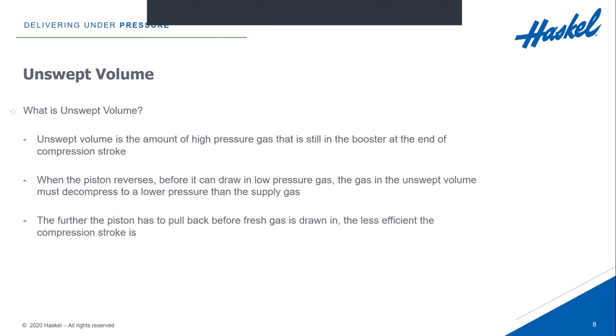Another important aspect of gas compression is the unswept volume inside the compression device. The unswept volume is the amount of high-pressure gas that's still in the booster at the end of the compression stroke. All compressors, no matter what the technology, will have some amount of unswept volume left in them at the end of the stroke. When the piston reverses, before it can draw in fresh low-pressure gas, that gas in the unswept volume has to decompress to a pressure lower than the supply gas to allow it to flow in. The further the piston has to pull back before gas is drawn in, the less efficient that compression stroke is.